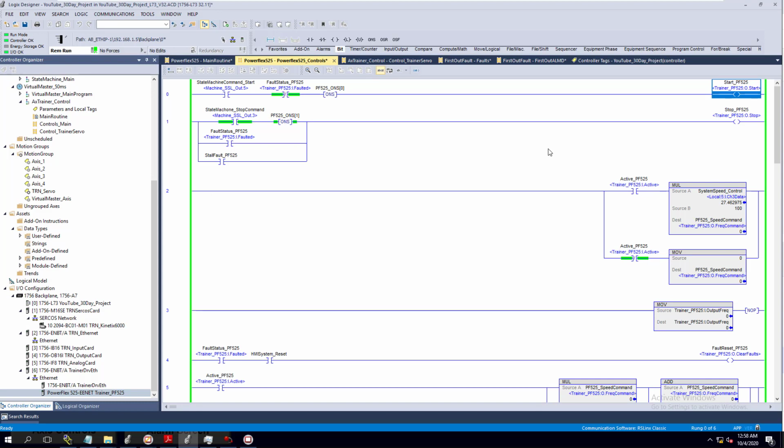So one shot to run, to latch that one shot in, because the drive logic is so fast, it latches the run in. That's the thing that a lot of people don't understand about the PowerFlex series of drives: the logic will catch that run. That's exactly why I'm talking about when you're failing safe. When you're failing to start, you definitely need to issue a stop command all the time. So even on a fail start, you would definitely come in and issue the stop, because you want to get that drive back into a happy state where it knows if you hit a start command again, it will start.